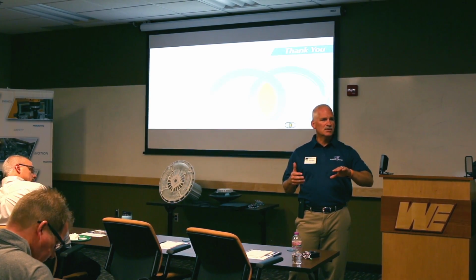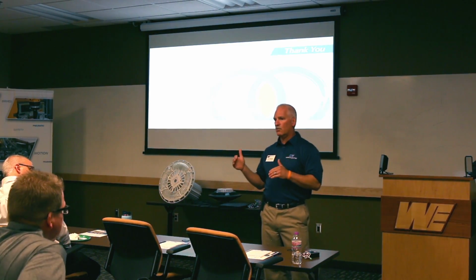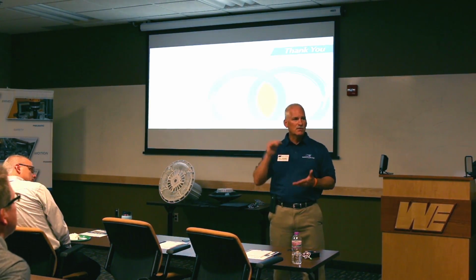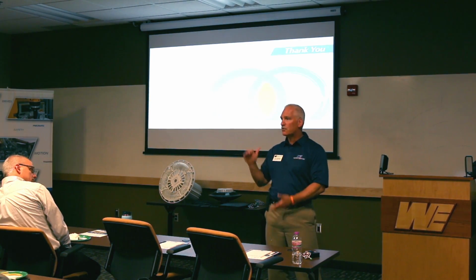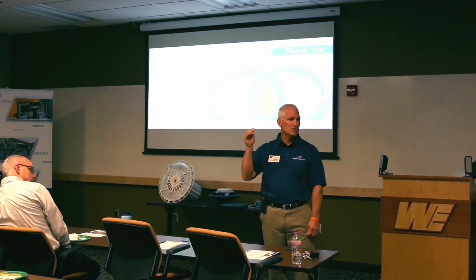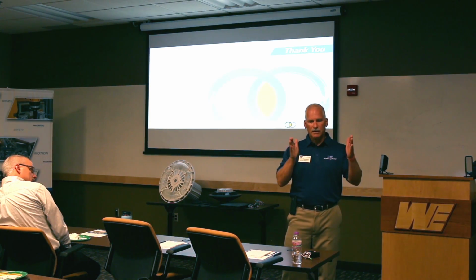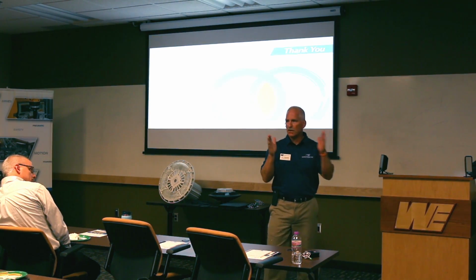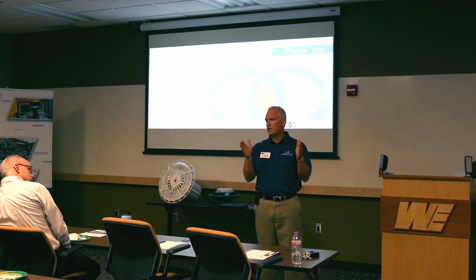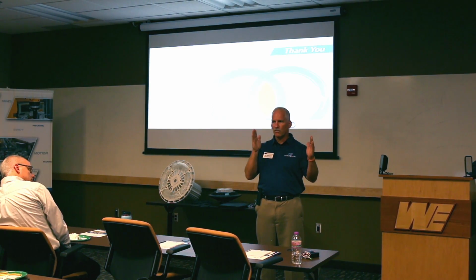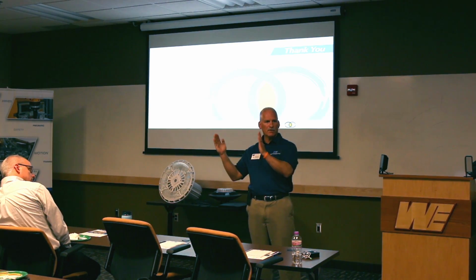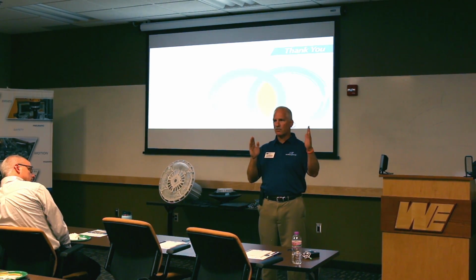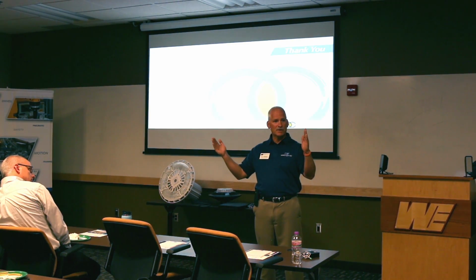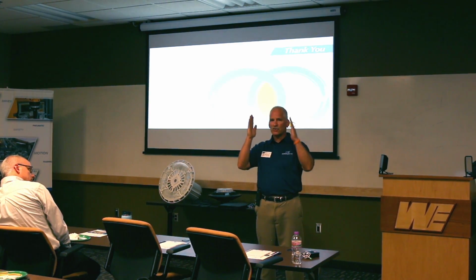The next piece is power, kilowatts. If you're asking for peaks from the utility, they're going to charge you for those peaks, even if you only used it once. And remember the 15-minute interval? A demand management situation looks at what you're doing over a 15-minute moving average. So if you start a large compressor on minute 1, don't start the next one until minute 16 or 17, because that gets averaged in there.